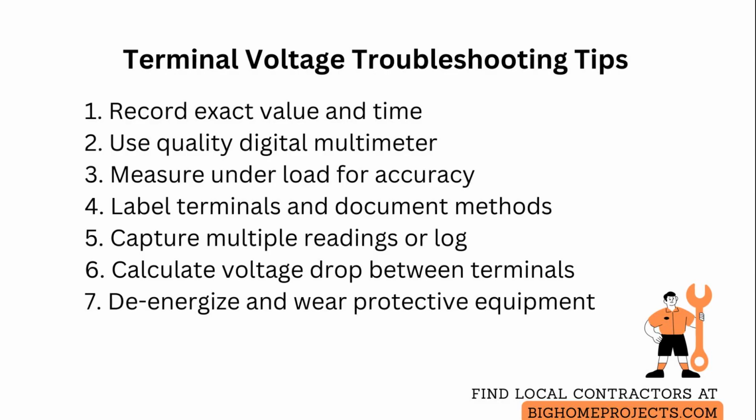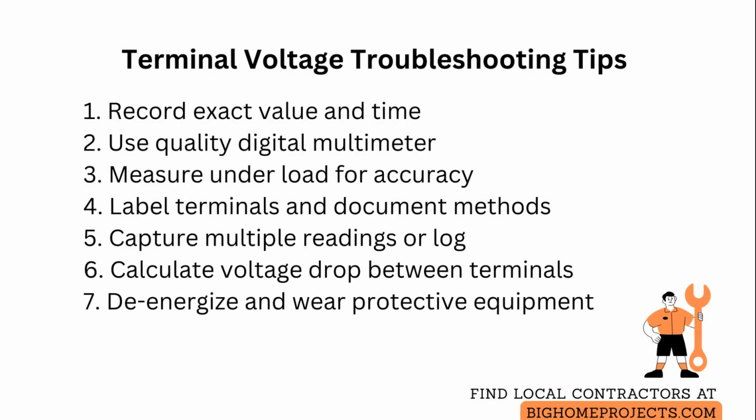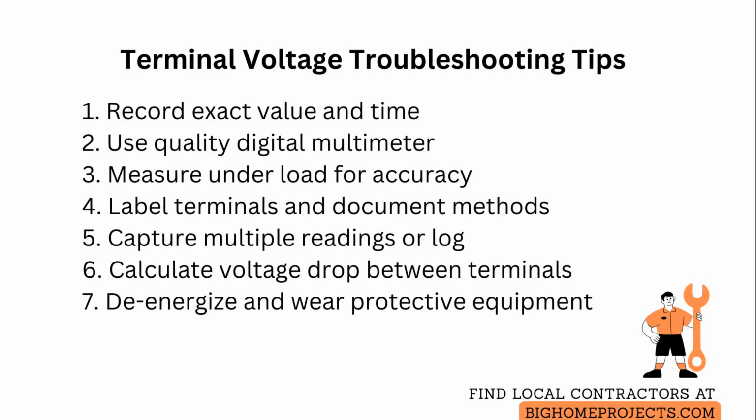If working on three-phase or multi-rail supplies, document phase-to-phase and phase-to-neutral voltages and the sequence to detect imbalance or phase loss. Explain that in three-phase systems, which distribute load, imbalance can indicate a failing motor, loose connection, or partial supply fault.